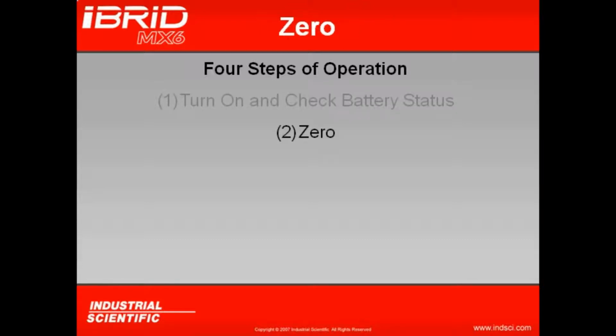The second step of operation will be to zero the instrument. Whenever we zero, we're using the ambient atmosphere as the instrument's zero reference point. 2 processes are going to take place when the instrument zeroes. The first process will be that the toxics and combustible sensors will be set to 0 to eliminate any type of negative or positive drift. The second process that the instrument will do during zeroing is it'll calibrate the oxygen sensor to the room air at 20.9%. We always want to ensure that whenever we zero the instrument, we zero only in clean air. If there's any contaminants in the air, that'll become part of the instrument's zero reference point.